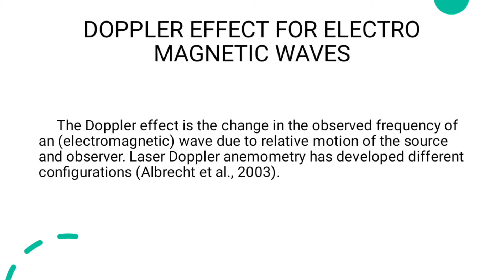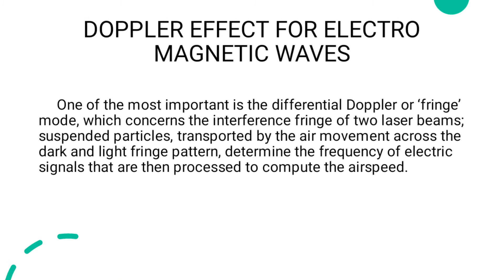Laser Doppler anemometry has developed different configurations. One of the most important is the differential Doppler fringe, which concerns the interference fringe of two laser beams. Suspended particles, transported by the air movement, cross the dark and light fringe pattern. This determines the frequency of electric signals that are then processed to compute the airspeed. The velocity of the suspended particles causes a Doppler shift in the frequency of the light that is scattered, and this is measured with a photodetector.